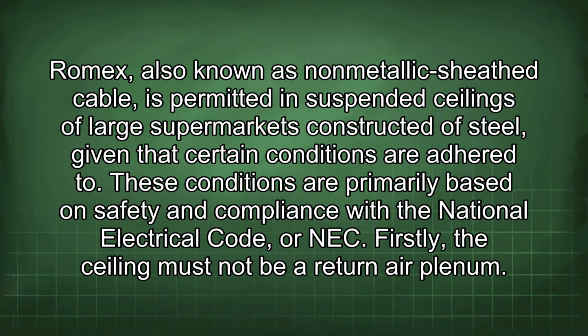Romex, also known as non-metallic sheath cable, is permitted in suspended ceilings of large supermarkets constructed of steel, given that certain conditions are adhered to. These conditions are primarily based on safety and compliance with the National Electrical Code, or NEC. Firstly, the ceiling must not be a return air plenum.